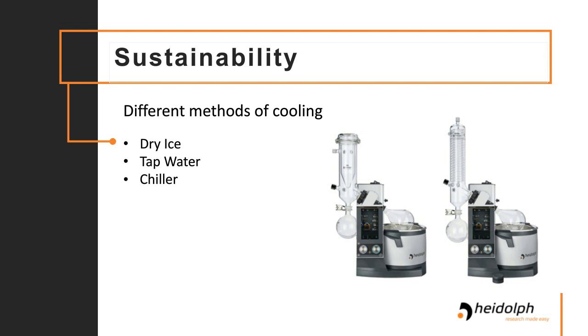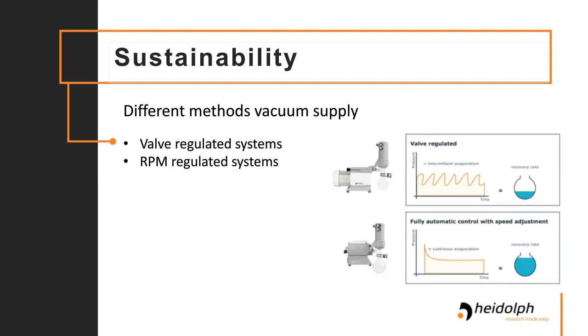Regarding the vacuum source for your rotary evaporator, there are two different kinds on the market. One is a diaphragm pump, which is a valve-regulated system. The other one is what Nate already mentioned, the RPM-regulated system.